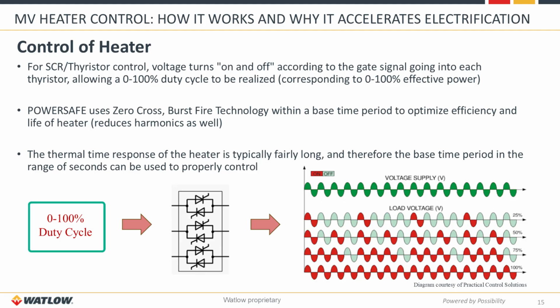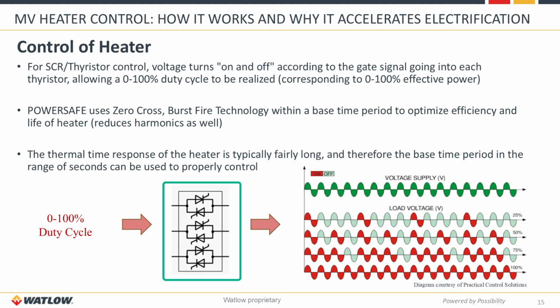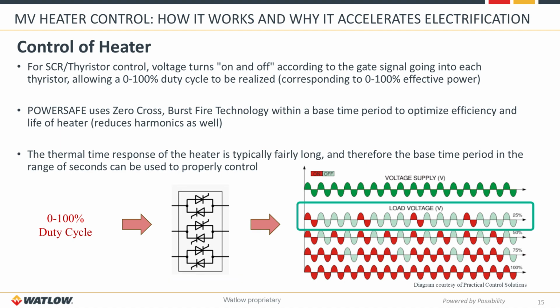So if you're using a DCS and you're providing a 0 to 100% duty cycle into our system and telling us you want, say, 25% power, we would gate fire the SCRs at a 25% ratio and thus get the graph here in the middle part of the screen, the 25%.